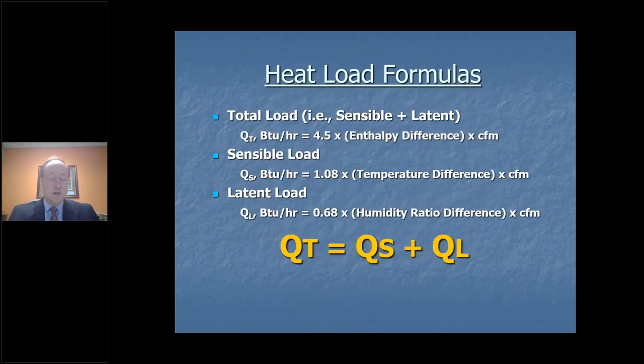These are three formulas that we use. So again, if you understand the psychrometric chart, you understand how to use a ductulator, and you know these three formulas right here, you can attack any HVAC issue out there. I'm confident of that. So if you want to look at the total load, this is the BTUs per hour times the factor right here, constant, and the difference in enthalpy times the cubic feet per minute running through that particular air handler. And that would give you the total load of that particular building, or let's say maybe what that particular air handler is capable of handling. And that gives you a combination of sensible and latent. If you wanted to break that down between sensible and latent, here are the formulas for that. And rather than spend a lot of time, we're going to do an example in just a minute with this last formula right here for the latent load, and hopefully it will make sense to you.